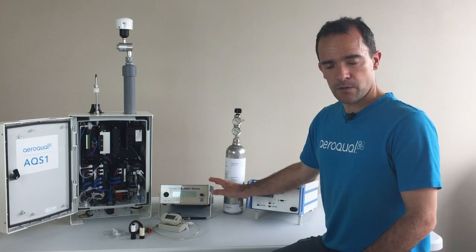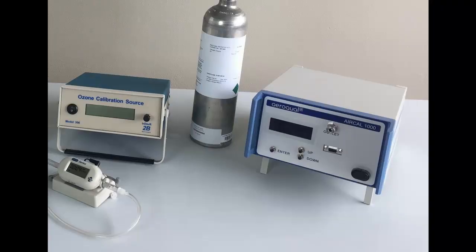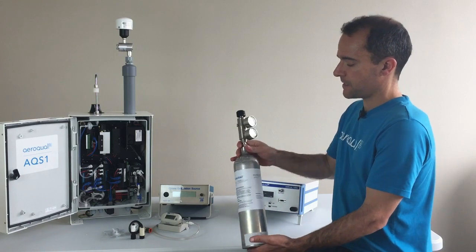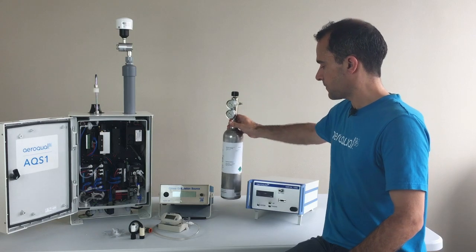To calibrate the Ozone module, if you have one in your AQS-1, we use the 2B Technologies Ozone Calibration Source — this is Aeroqual part number 03 Cal. We also have the AirCal 1000 for delivering a controlled diluted gas of NO2 or isobutene. And of course you would purchase your calibration gas in exactly the same way for the AQS-1 as you would for the AQM 65.